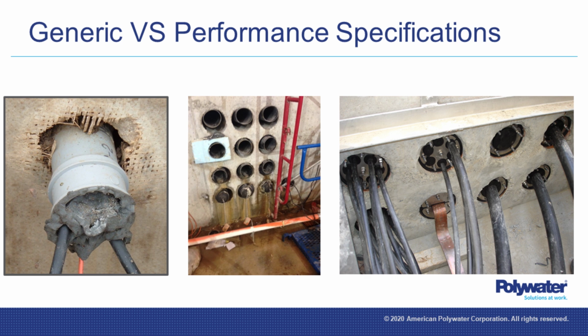Because the cable construction is different, the sidewall pressures will be different, and they will tell you what the derating is, meaning they'll tell you what you can achieve. So they might say you can go to 80% or 90% of that sidewall pulling force. You really need to get that from the manufacturer.